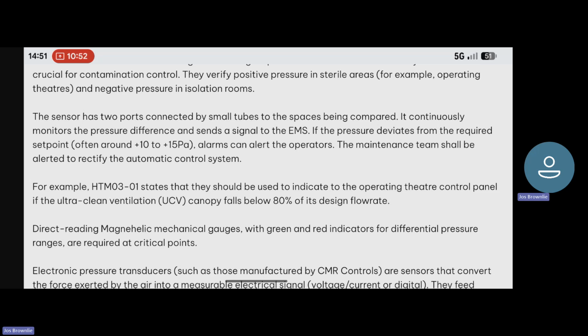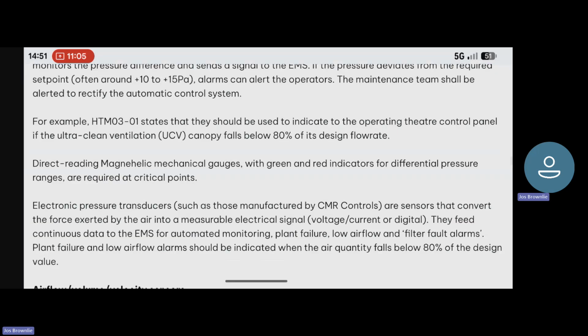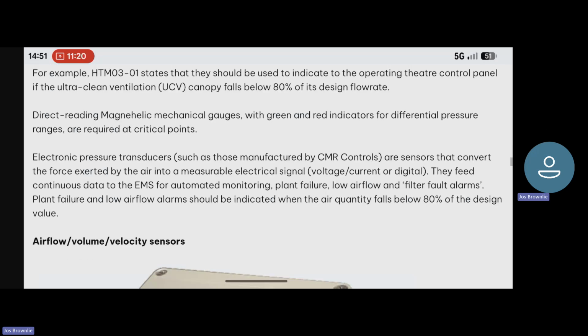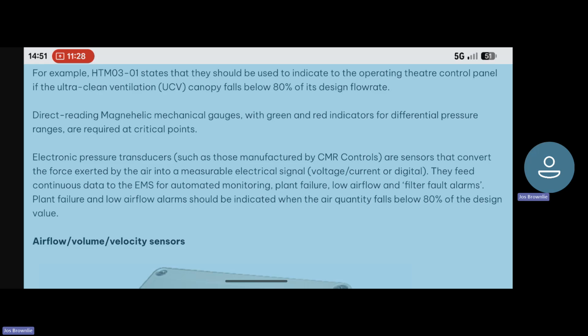If the pressure deviates from the required set point, often around 10 to 15 pascals positive pressure, alarms can alert the operators. The maintenance team shall be alerted to rectify the automatic control system. For example, HTM 03-01 states that they should be used to indicate to the operating theatre control panel if the ultra-clean ventilation, or UCV, canopy falls below 80% of its designed flow rate. Direct reading Magnehelic mechanical gauges with green and red indicators for differential pressure ranges are required at critical points.